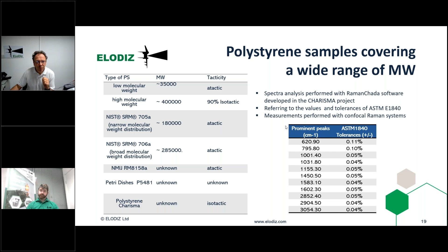We have used as well, for example, a reference point from the Institute of Metrology in Japan, which has characterized fully crystalline silicon material, and they say the center of this peak should be 520.45 plus minus a certain deviation. We have analyzed a number of silicon samples to observe what deviation we can observe from the different ones. Then we have analyzed polystyrene. Polystyrene, for example, is one of the reference materials referred to by NIST and by the ASTM. We have analyzed, okay, from all the different polystyrenes, which one is the one that we need to use? Because right now the ASTM only refers to polystyrene. Well, there is a lot of polystyrene, unfortunately.